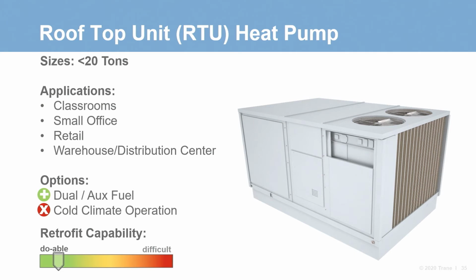Unlike split systems, there are no line sets external to the unit, so that's not going to be a concern. However, standard rooftop units cannot be retrofitted with heat pump components, so the entire unit will need to be replaced. Again, with any heat pump retrofit, electrical service must be checked to make sure it can handle the heat pump duty. All right, next is packaged terminal heat pumps.